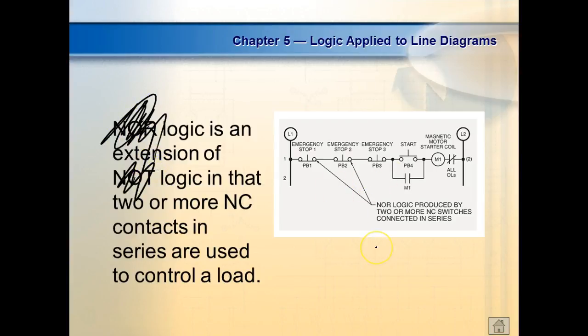So what is this? Well, a lot of people say, what's an AND? They're in series. This is not an AND. So any of these will turn the load what? Off. Any. So when I say any, it's either an OR or it's a NOR. Here, any of them turns the load off. So what's this? That's a NOR. But the problem is people will jump on it, if they're in series, it's an AND, and then they don't pay attention to the logic. So ANDs and ORs turn the load on, NOTs and NORs turn the load what? Off. Here I said what? Any of those push buttons will turn it off. If I use the term any, it's either going to be an OR, a NOR, or what? Normally closed in series is a NOR.